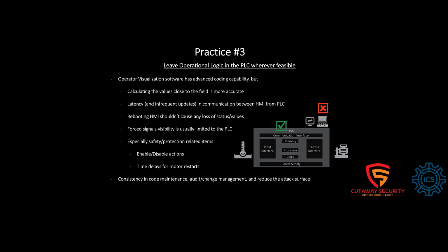Okay. Even in DCS, traditional DCSs, the reason why that software ended up becoming more powerful is it's just easy for an operator, for example, to add an alarm for himself or herself without having to ask the engineer to do it for them in the PLC, right? Hey, I want to have this additional alert, I'm monitoring this pump and I want to know this discharge pressure be on a certain level, even if it's not a high alarm. An operator can do it on the HMI itself if they have access to it, obviously, and there is a functionality available. So over time, it became possible for even integrators to add that logic there, because then they don't have to touch the PLC code, open that PLC programming environment. They can just do it from the HMI itself without going to their engineering workstation or fire up their laptop to do it on the PLC code.